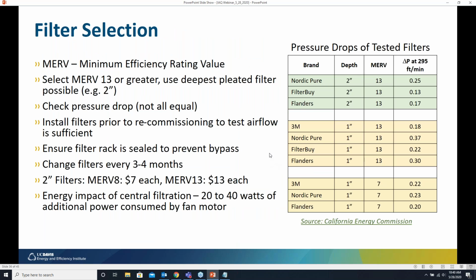Okay, I want to switch gears and talk about filter selection. Rengie clarified that even though virus particles are small, they're often contained within droplets, and so some of them can be removed by HVAC filters. We're recommending, consistent with ASHRAE, to use MERV 13 filters or better, and to use the deepest pleated filter possible, for example 2 inches deep, to improve its effectiveness and to reduce the amount of filter changes required.